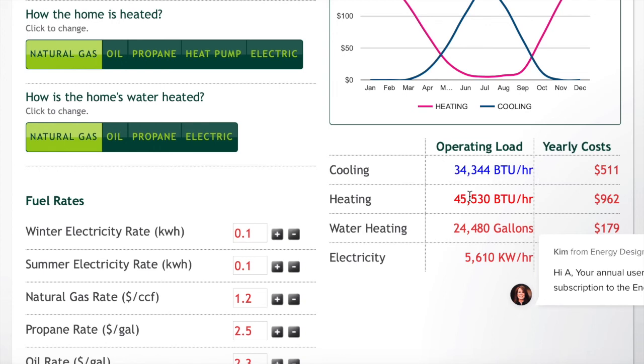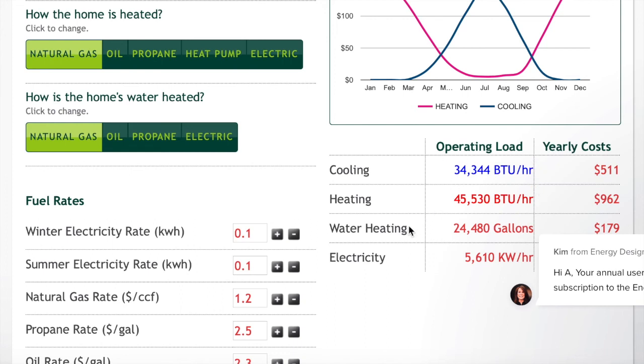Next is the cooling load, which tells us how much heat we need to remove. To properly satisfy the thermostat, we need to remove at least 34,344 BTUs of heat per hour. As covered in a previous video, one ton of AC removes 12,000 BTUs of heat, so dividing 34,344 by 12,000 gives us about 2.8 — meaning we need at least a three-ton unit. A three-ton unit removes up to 36,000 BTUs per hour, which fully satisfies that 34,000 BTU requirement.